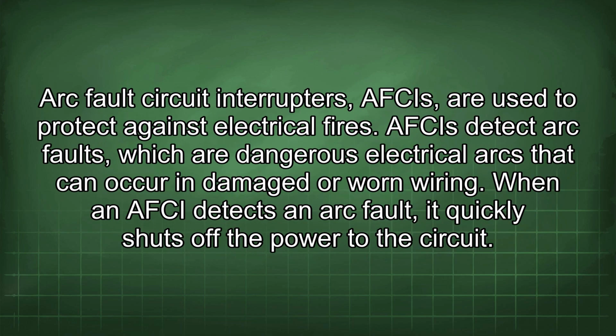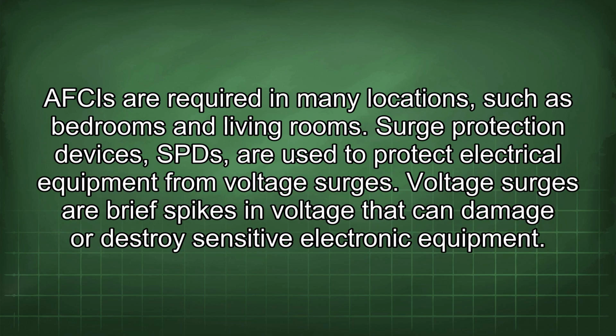Arc fault circuit interrupters, or AFCIs, are used to protect against electrical fires. AFCIs detect arc faults, which are dangerous electrical arcs that can occur in damaged or worn wiring. When an AFCI detects an arc fault, it quickly shuts off the power to the circuit. AFCIs are required in many locations, such as bedrooms and living rooms.